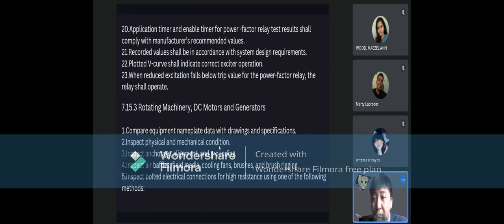20. Application timer and enable timer for power factor relay test result shall comply with manufacturer recommended values. 21. Record values shall be in accordance with system design requirements. 22. Plotted values V curve shall indicate correct exciter operation. 23. When reduced excitation falls below the trip value for the power factor relay, the relay shall operate.